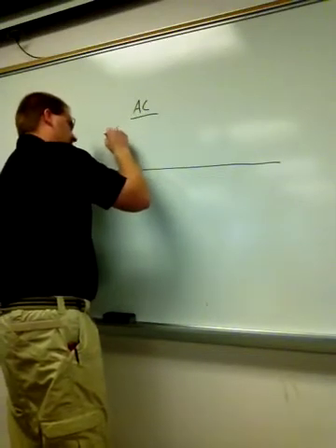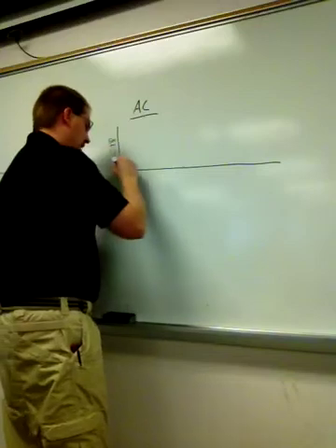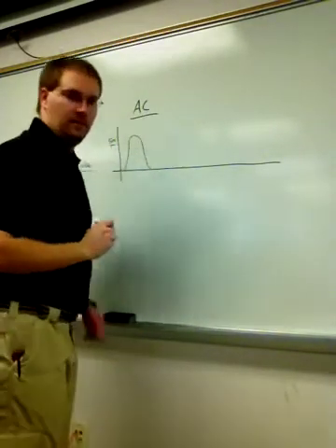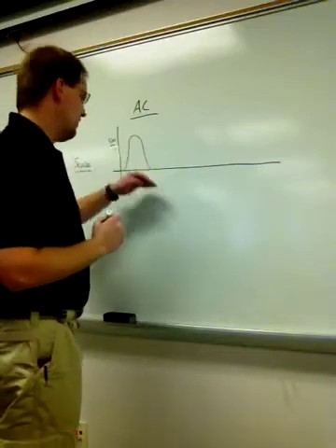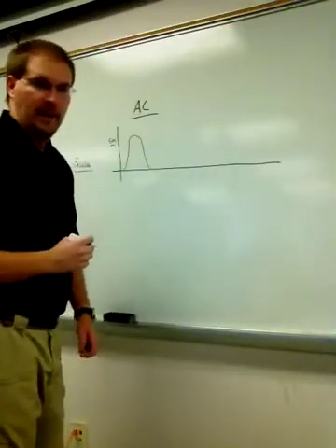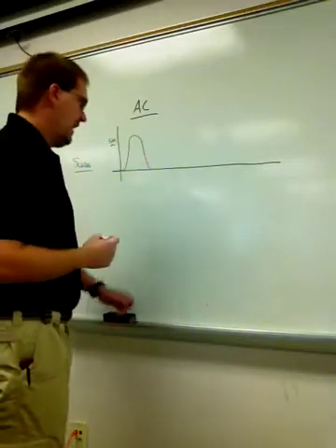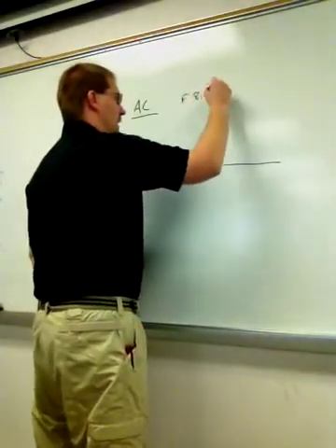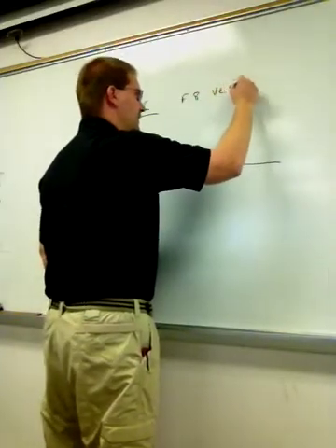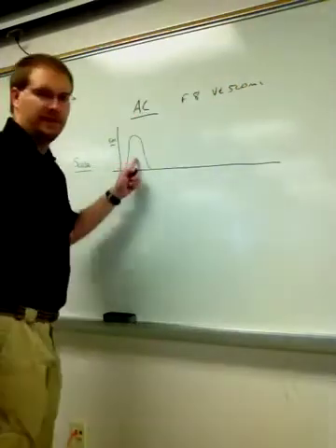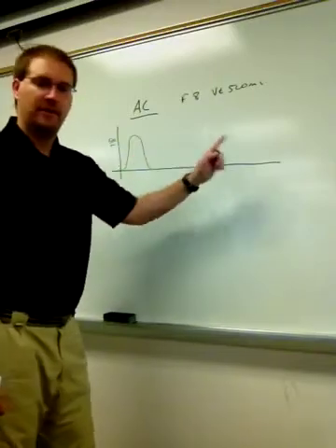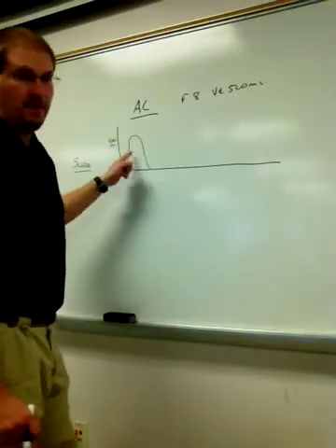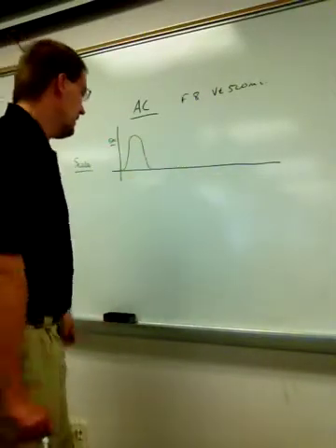We'll look at a volume time scalar, just looking at the volume of gas delivered into the lungs. If I have somebody in assist control with a volume of 500 milliliters, the ventilator will deliver that volume, the patient gets the volume, they exhale, and so on. If I have a rate of 8 and a tidal volume of 500 milliliters, the ventilator is going to deliver 8 breaths at 500 mils per breath, 8 breaths a minute, 500 mils per breath.